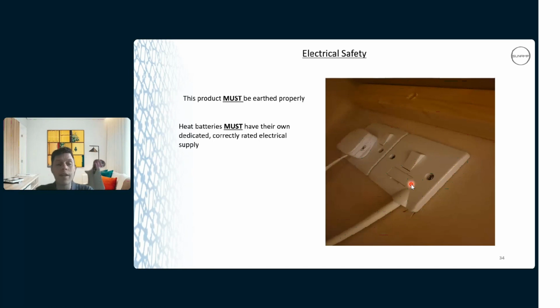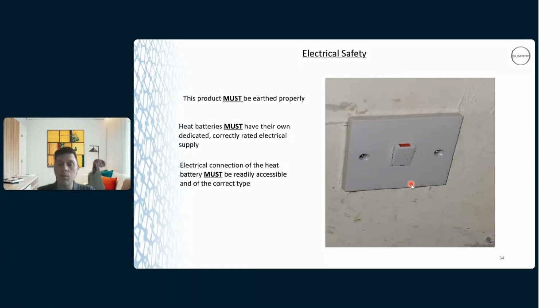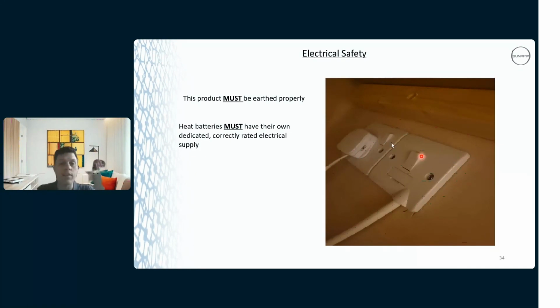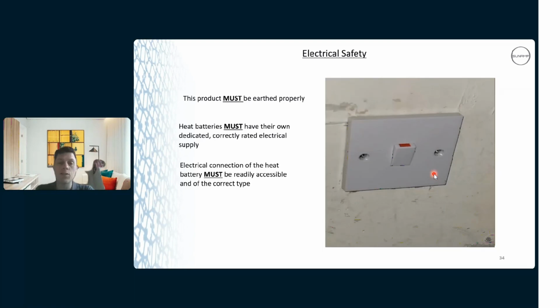The minimum requirement for a double pole isolator is 16 amps. But when you search for a 16 amp isolator, it comes up with a quite industrial looking rotary isolator, so you go up to the next size, 20 amps. We just want to make sure that this isolating switch is capable of withstanding the current going through it, because units will run at 12 and a half amps. Although these might be rated at 13, because you're touching the higher limits of what that switch can handle, any resistance built up in the contacts is going to cause a burnout and make the switch go brittle and fail. I've seen loads of them. So just make sure you've got the right size. A 20 amp double pole isolating switch is the right one to use.